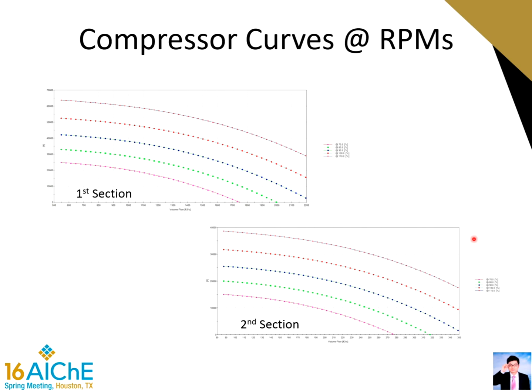To better model the overall cycle performance, the compressor curves are also input to the dynamic simulator. The x-axis is the actual volume flow and the y-axis is the head. Different curves represent the performance at different RPM. If the compressor guide vanes are adjustable, those curves can be input to the simulator as well.